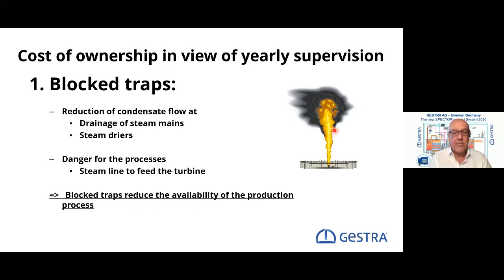It's just a recommendation. Especially if you have a seasonal operation and during the summertime you have no heating process, then you have oxidation by air and corrosion during the summer, and at the beginning of the autumn you find your problem. And don't forget, a steam trap is a control valve which works with a rather high pressure drop and a small lift of its orifice. And this, of course, always makes it sensitive to dirt. If you have a 365-day operation, 24 hours a day, then normally we have no dirt problems, because no corrosion appears, because no oxygen is inside the system. The on-off systems are the main problem.